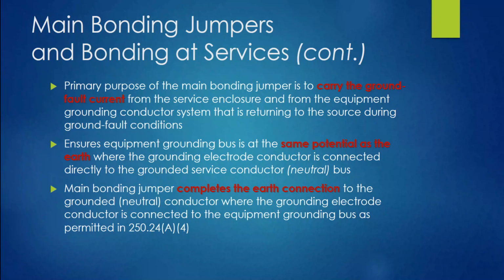Now, the primary purpose of the main bonding jumper is to carry the ground fault current from the service enclosure, whatever might energize the enclosure on a ground fault condition, and from the equipment grounding conductor system that is returning to the source during a ground fault condition. Okay, so that's one thing.